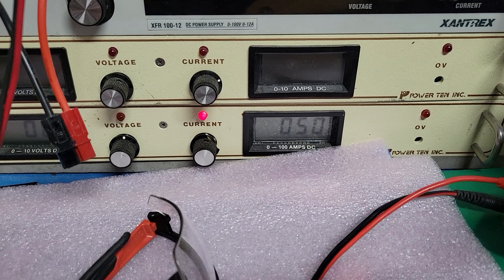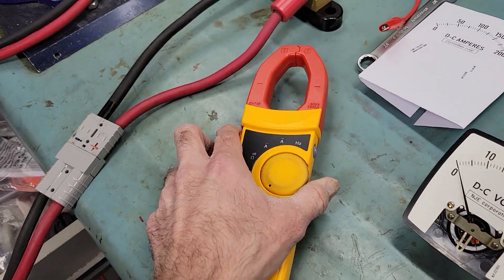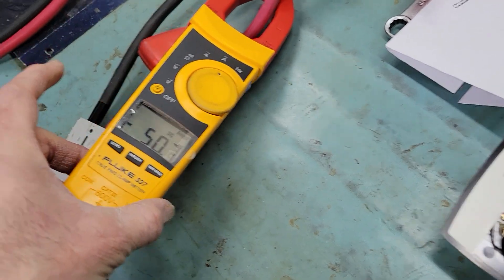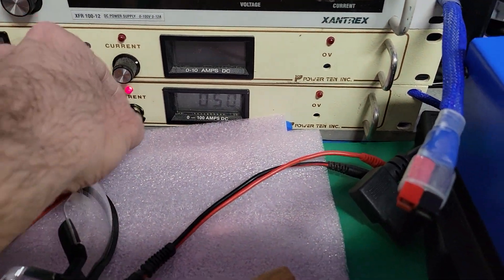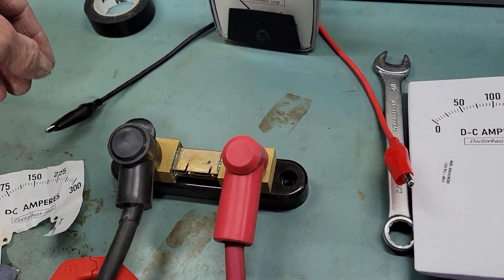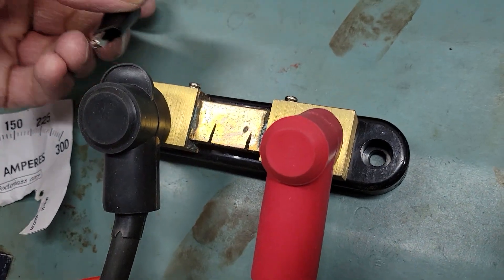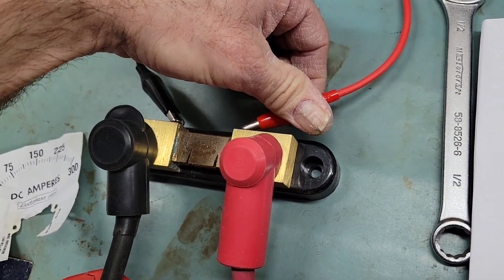It's good now for 50 amps. So there's 50 amps going through these conductors here. I will check with the precision meter. I will just zero it right now exactly, so it is ready. Here it's displaying 51.4, but the display of this one is not pretty accurate. I'm more confident on the Fluke meter here. Let's say 50.7 amps. So there's 50.7 amps going through this shunt here. I will connect it here. You see there's two screws and those screws correspond exactly to the location on this resistance where there is the corresponding voltage drop in millivolts.